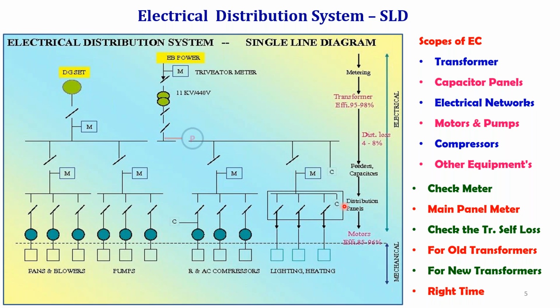Now, a very important point is you always have a check meter connected with the tri-vector meter. Check meter is also one of the important meters. Most of the industries will have a check meter. The check meter is used to correlate the readings taken by the main meter. Of course, the main meter reading will only be considered for the billing, but the check meter reading will also be taken into account if you have any discrepancy in the billing system.